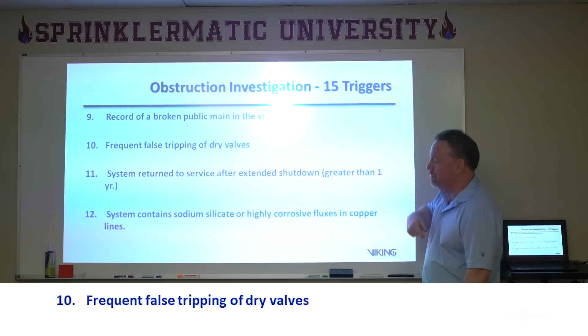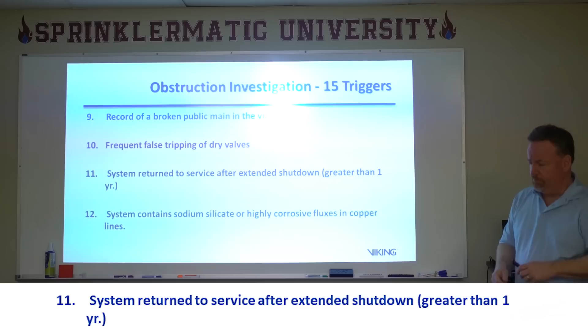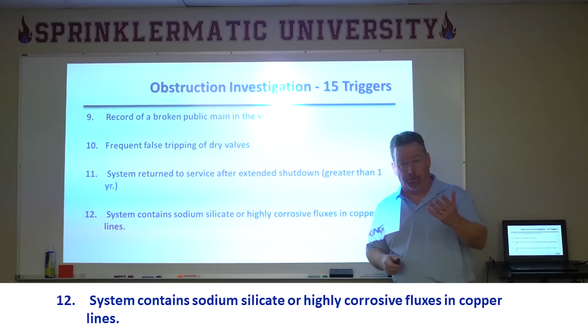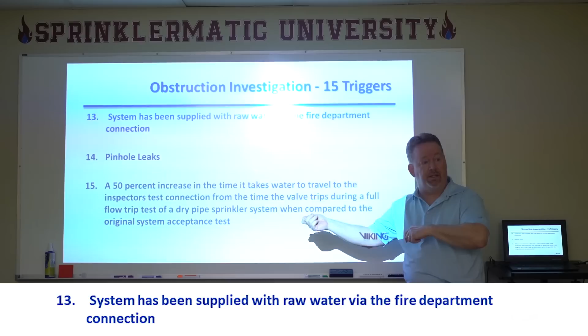Frequent false trippings of the dry valve, indicating there might be obstructive material in the valve itself. If the system is returned to service after an extended shutdown, greater than one year: say I shut my system down altogether, I've gotten approval, the building's been evacuated, it's an abandoned building, but in order to save the system I've shut it down, and now I'm putting it back online. Any system that contains sodium silicate or highly corrosive fluxes in the copper lines, if you've got copper piping, we're going to need to do an obstruction investigation. If the system has been supplied with a raw water source from the fire department, say they draft out of a pond and pump it into my system, I'm going to do an obstruction investigation.